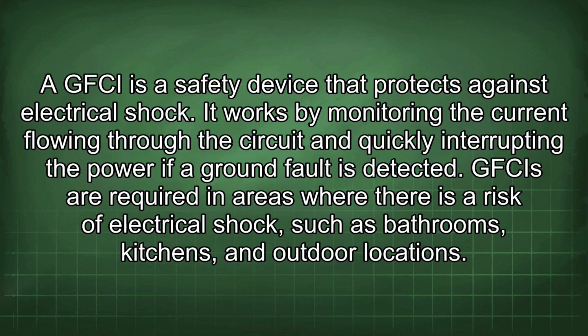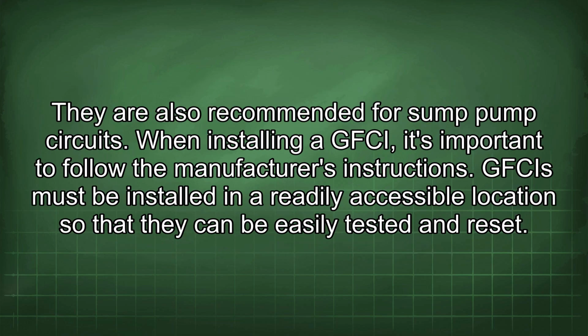It works by monitoring the current flowing through the circuit and quickly interrupting the power if a ground fault is detected. GFCIs are required in areas where there is a risk of electrical shock, such as bathrooms, kitchens, and outdoor locations. They are also recommended for sump pump circuits. When installing a GFCI, it's important to follow the manufacturer's instructions. GFCIs must be installed in a readily accessible location so that they can be easily tested and reset.